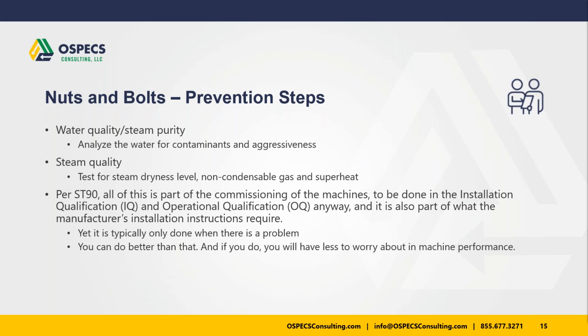So what do you do? Well, you analyze the water. That means water out of the taps that are connected to the same lines that feed the washer disinfectors or are being used for manual cleaning. And you collect condensate. That's where you get facilities involved because usually they have the tools to do that from the steam at the sterilizer. I don't care what happens in the boiler plant. The sterilizer isn't in the boiler plant. The sterilizer is where you're using it. So you need to safely collect steam condensate for analysis. Analysis can be done with test strips that you can get from industrial supply houses, or you can send it out to a laboratory.